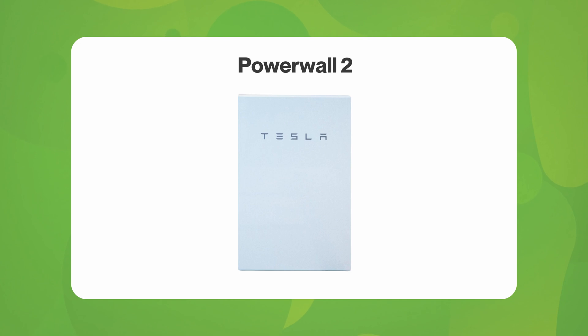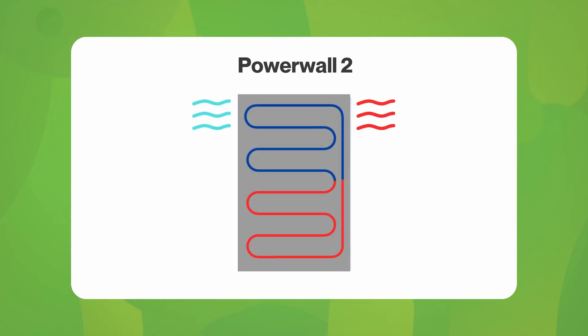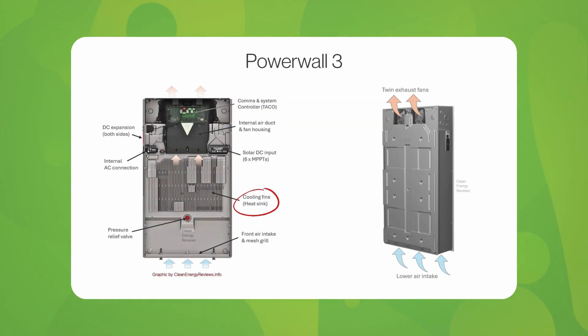Our company prides itself on never fitting Powerwall inside a home, as Powerwall is designed to be outside. Powerwall 2 was water-cooled, but Tesla found it to be rarely activated — it worked by taking heat from the internal power electronics and exchanging it to liquid coolant circulating throughout the unit. Powerwall 3 advances on this by adding a new individual cell cooling architecture, heat mode, and flood resistance.